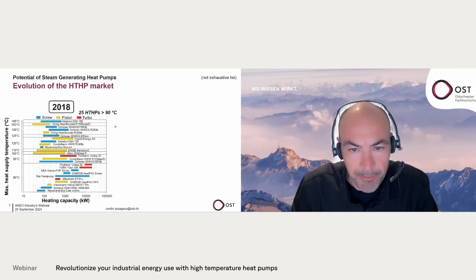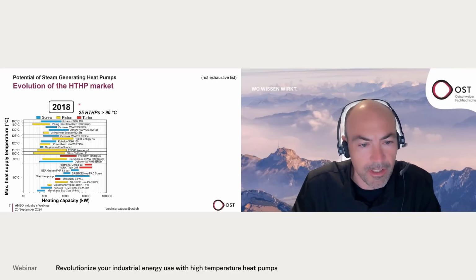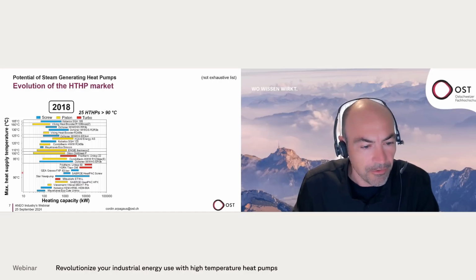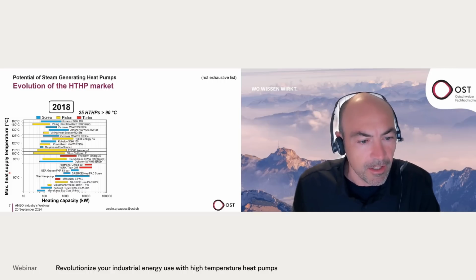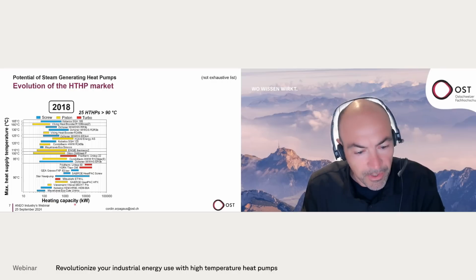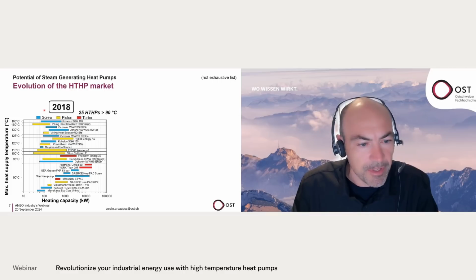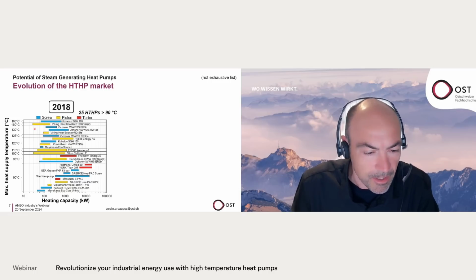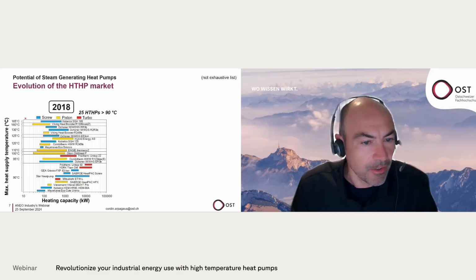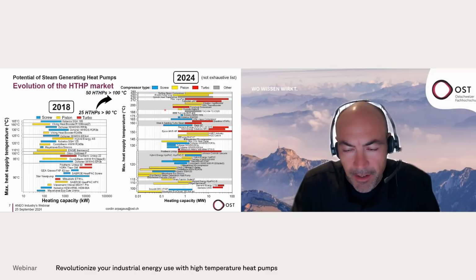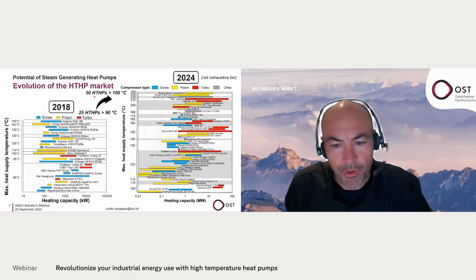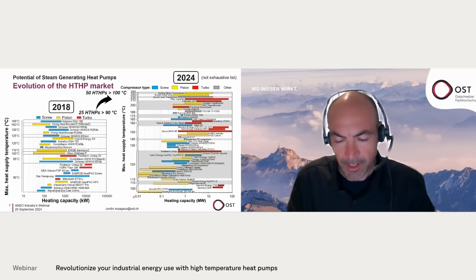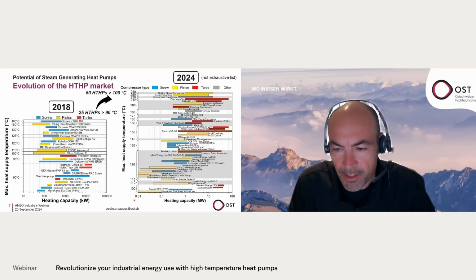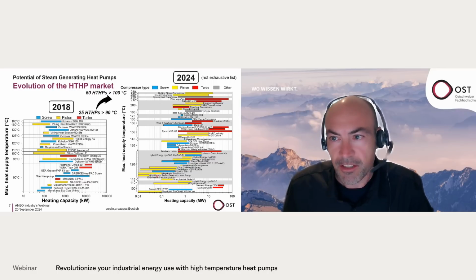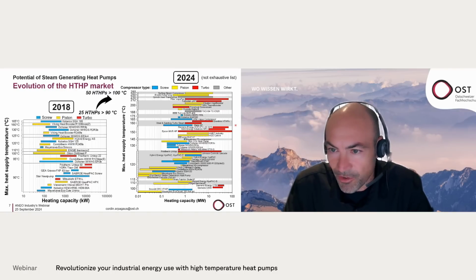I made a review on heat pump suppliers and manufacturers, and here is the overview from 2018, so 6 years ago. This shows different heat pump products as a function of the supply temperature that these heat pumps could achieve, and also as a function of heating capacity. The colors are the compressor types, and we saw already then that there are several heat pump manufacturers providing these heat pumps with supply temperatures over 90 degrees up to 160 degrees. Now, 6 years later, this market has developed quite a lot. Now there are more than 50 heat pump products that provide heat over 100 degrees. So the 90 degrees is not even shown on this list. This shows the evolution of this market, and it is a non-exhaustive list. For example, the Chinese products are not shown.